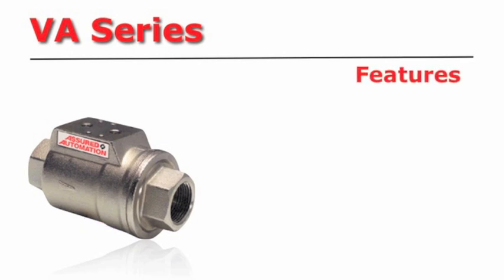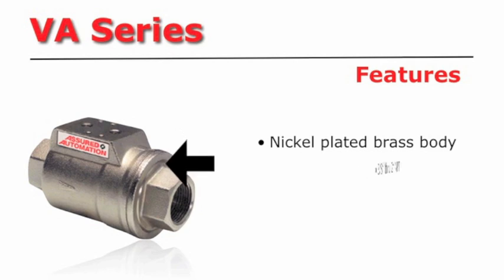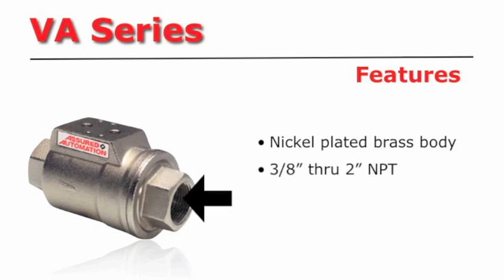The body and internals are nickel-plated brass. The end connections are available from 3/8 inch through 2 inch NPT or metric G thread upon special order. Valve pressure rating is industrial vacuum to 150 PSIG.